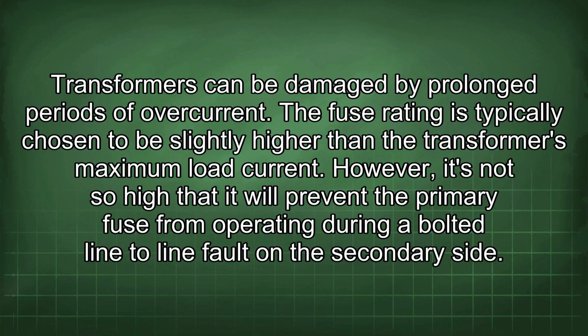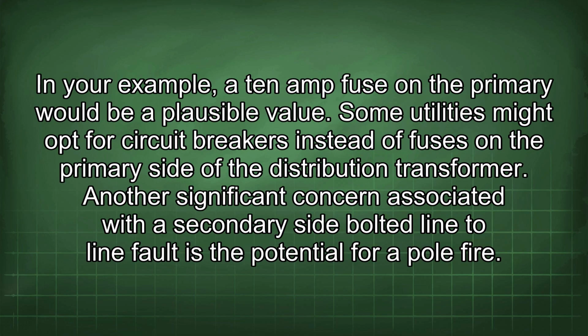The fuse rating is typically chosen to be slightly higher than the transformer's maximum load current. However, it's not so high that it will prevent the primary fuse from operating during a bolted line-to-line fault on the secondary side. In your example, a 10 amp fuse on the primary would be a plausible value. Some utilities might opt for circuit breakers instead of fuses on the primary side of the distribution transformer.